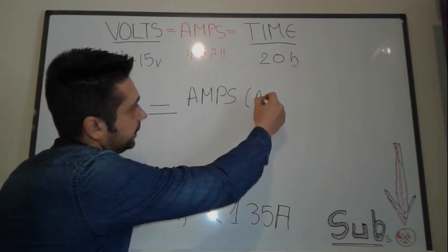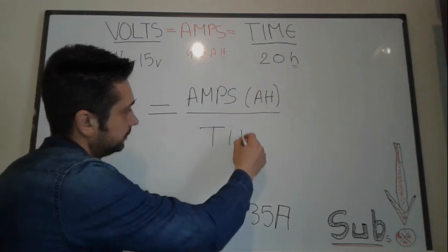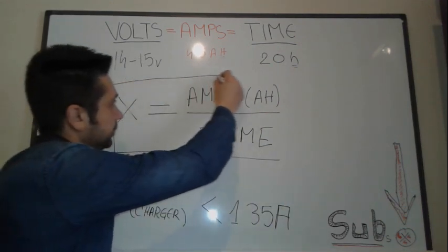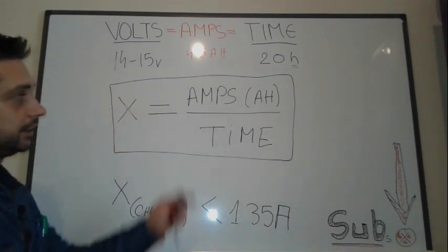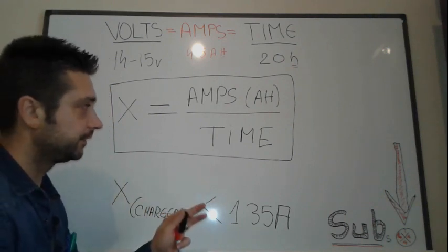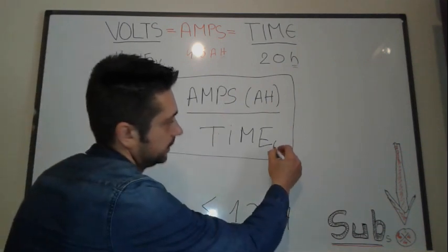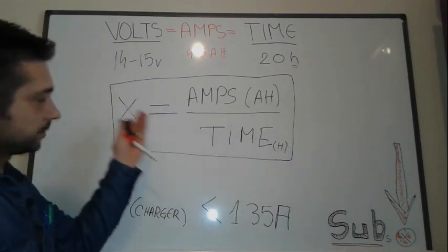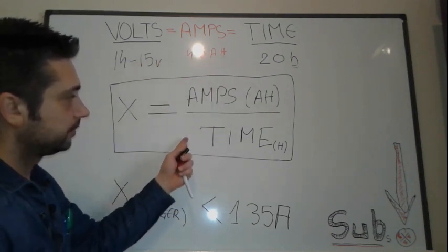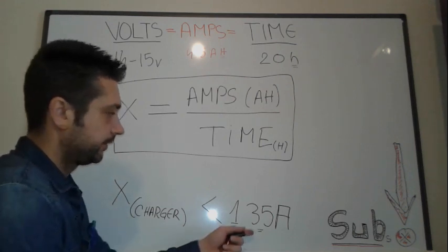Which should be measured in AH, not just plain simple amps, over or divided by time. So this is our formula for finding the needed current for each and every 12 volt battery to calculate how big is going to be your charger. With the help of this formula you're going to know that it should be less than 135 amps.